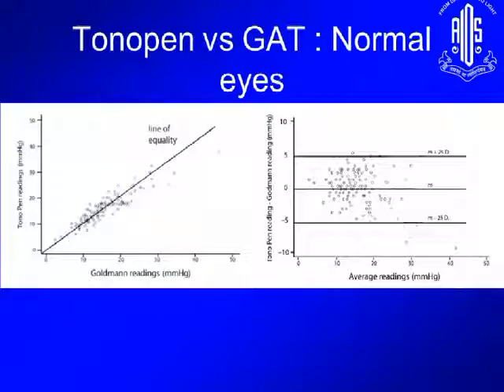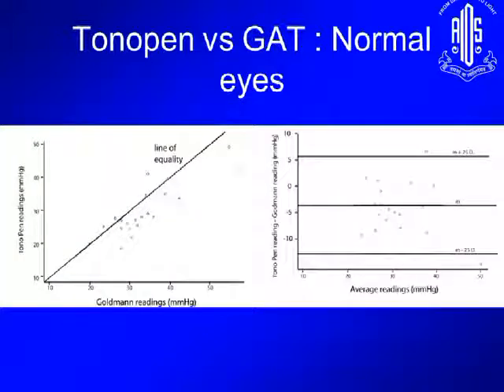So when you look at Tono-Pen versus Goldmann applanation tonometry in normal eyes, if you look at this line of equality, you find that all those readings are clustered around it, and the mean difference in a normal eye is 0. That means both are very, very close to each other. But the range of differences, even with this mean difference, is -5 to +5. So 95% of the time, your intraocular pressure readings in a normal eye with the Tono-Pen will range from 5 mm less to 5 mm more of normal.